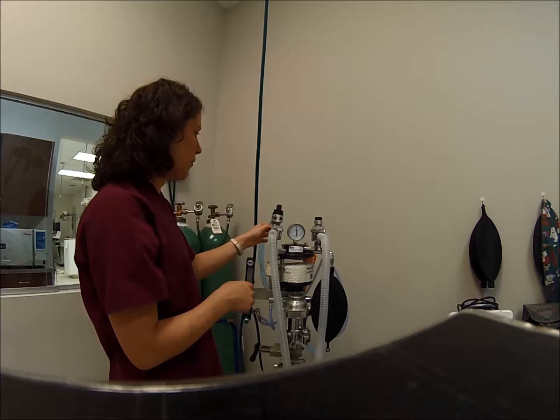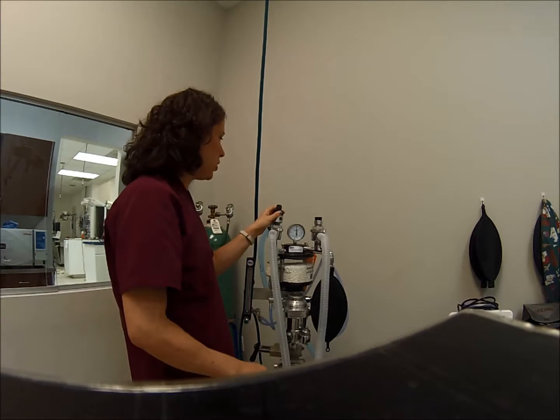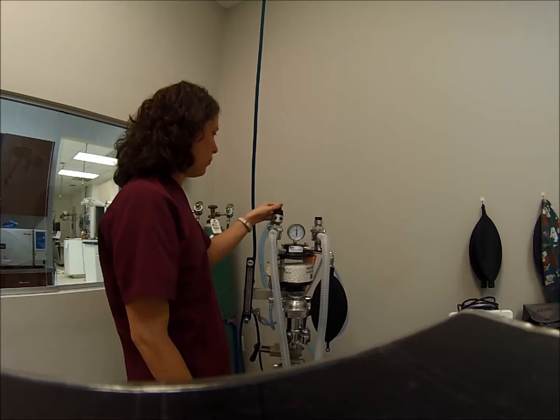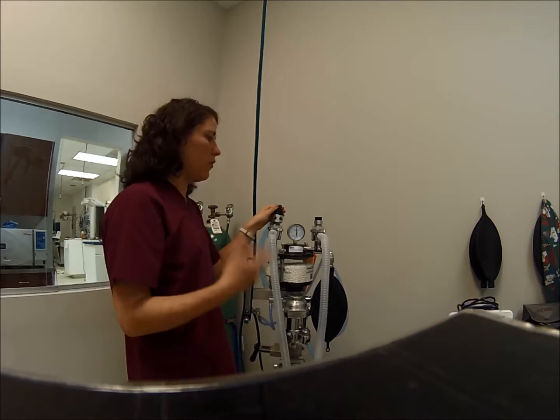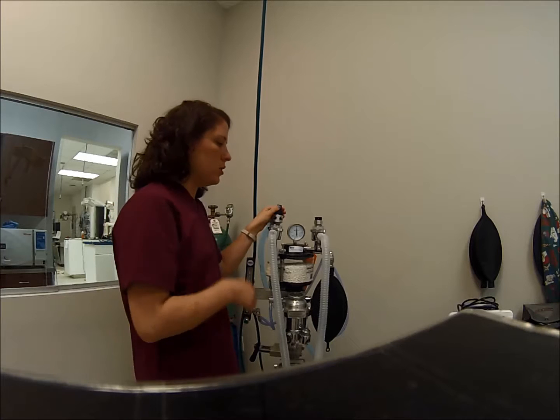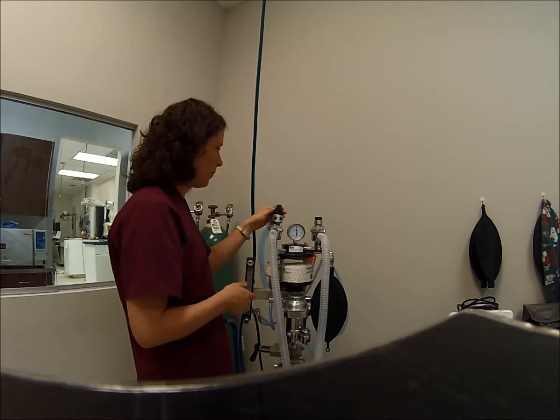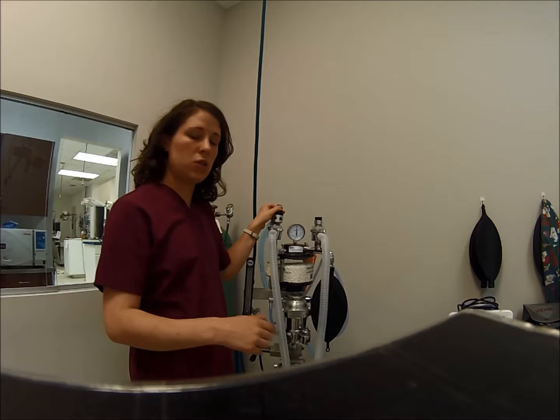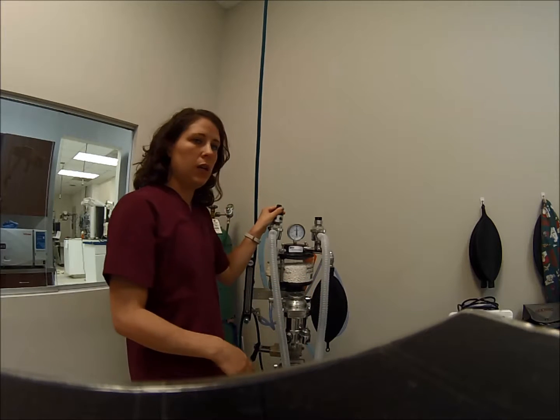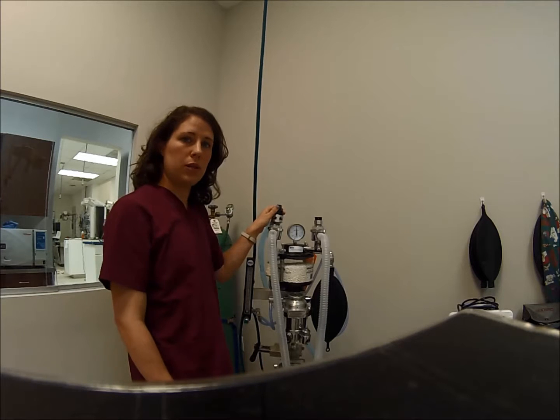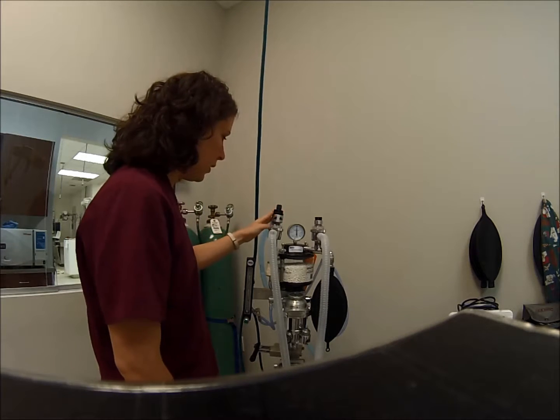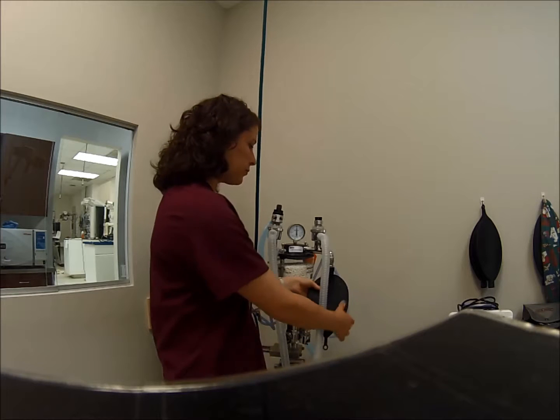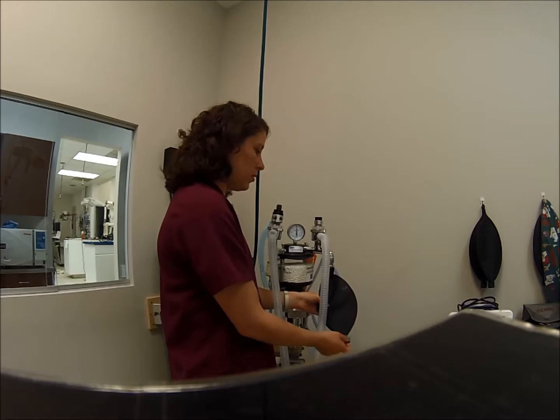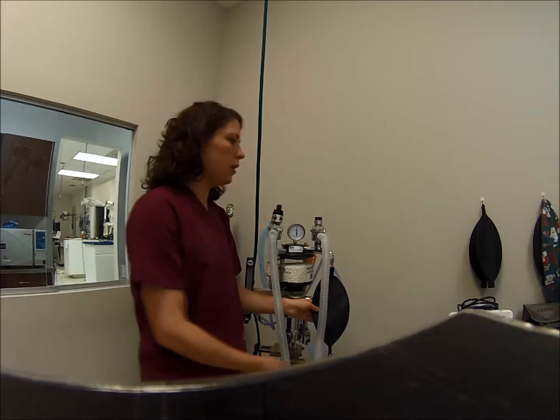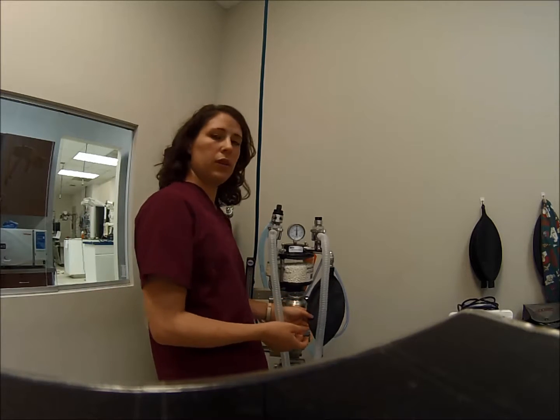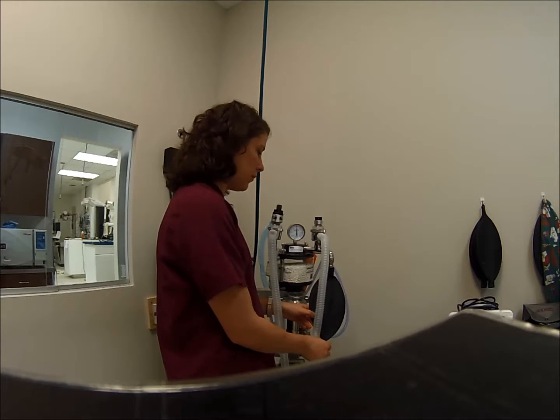On top of my expiratory valve is my pop-off valve, which can vent the system when it's in an open position to prevent buildup of pressure within the circuit. The only time it should be in a closed position is when you're manually ventilating the patient. It should never be left closed, always left in an open position. That leads me to my reservoir bag here. These come in a few different sizes. This is a 3 liter, but we carry bags up to 5 liters, depending on the size of the patient.